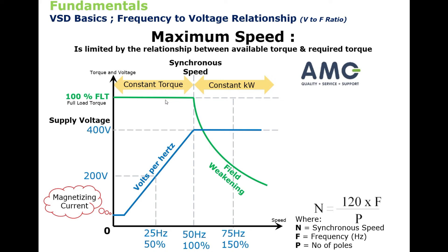If we overspeed the motor, there's not enough voltage in the variable speed drive to achieve the voltage required to flux the iron correctly. So above 50 Hertz, the system becomes constant kilowatts, where it was constant torque below 50 Hertz.